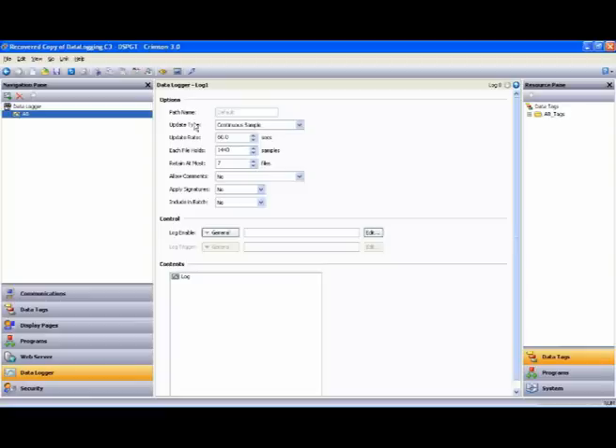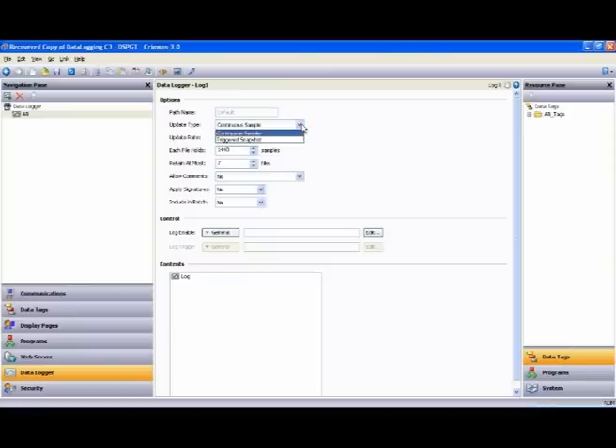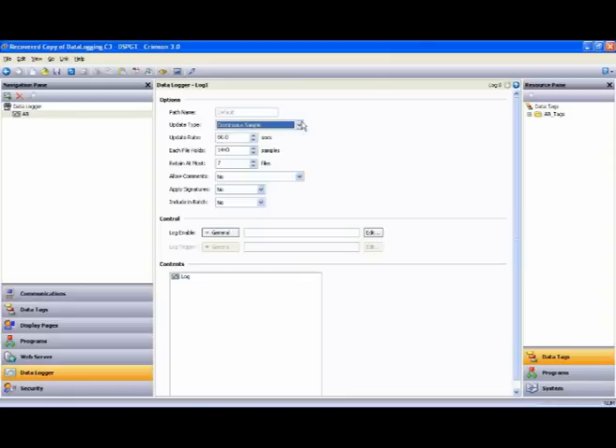Looking at the options for this log, you'll see two update types. You'll notice continuous sample, which allows the user to program the rate at which the samples update, or triggered snapshot, whereby you specify an event or condition that causes the logged update on each occurrence of the event or condition. We will use continuous sample. The update rate is simply how often you want to record a sample. Let's make that two.